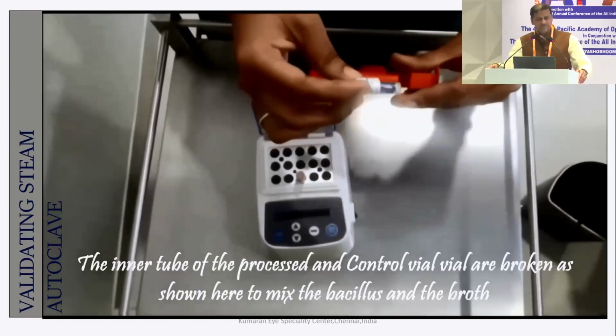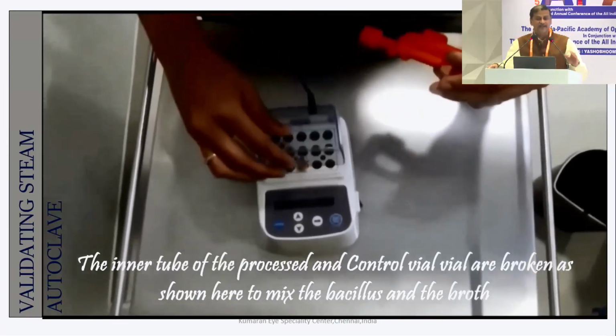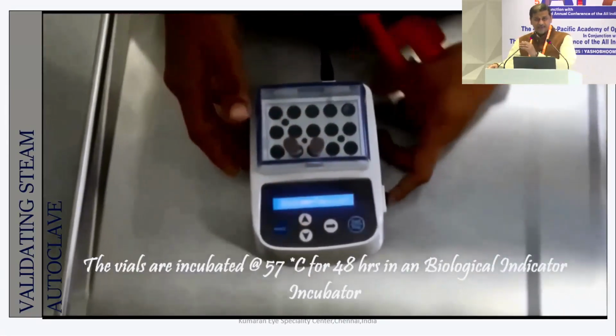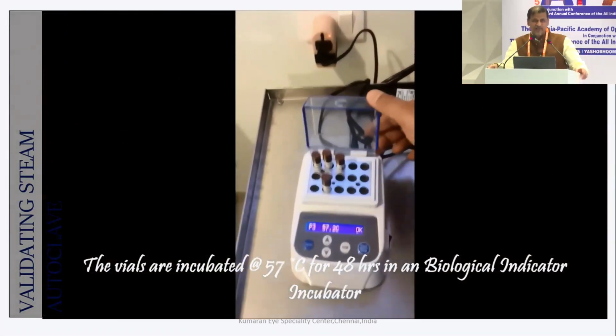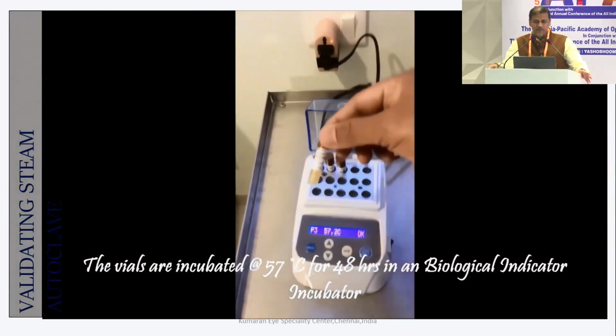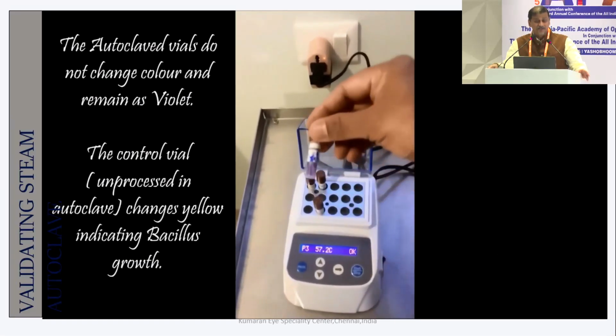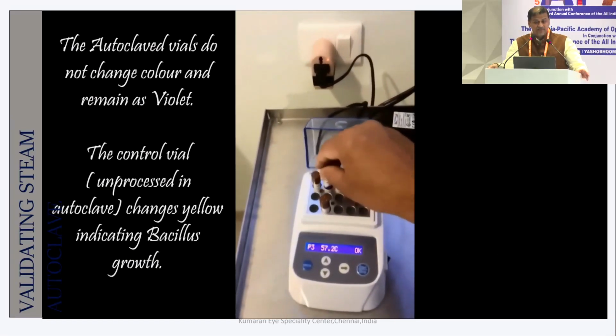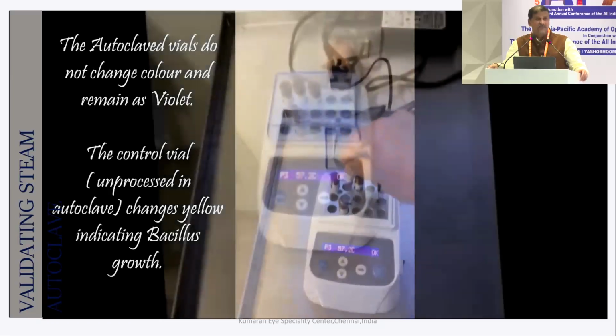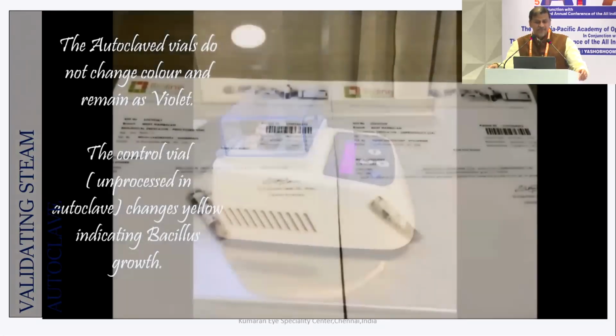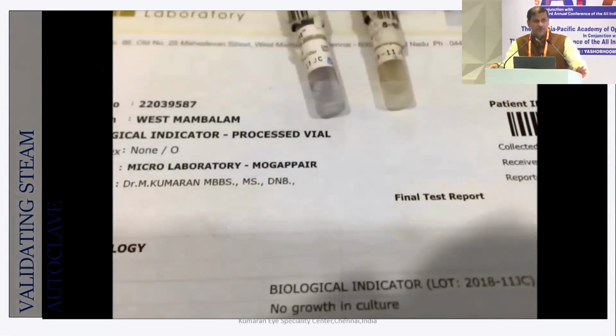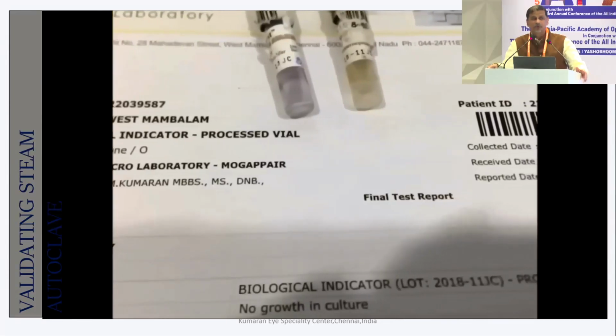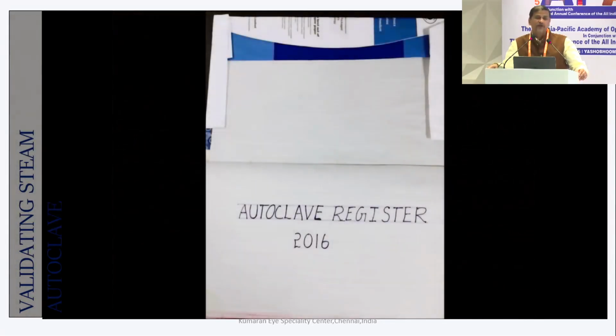It is incubated at 57 degrees Celsius for 48 hours. It is based on the fact that for the one kept outside, the bacillus has not been deactivated. So after 48 hours, you'll find that it has grown and the color changes to yellow, whereas the one which is kept inside doesn't change color because the bacillus has been killed. So this is the basic, and the biological indicator is the most important indicator which would help you to prove that your load is sterile.